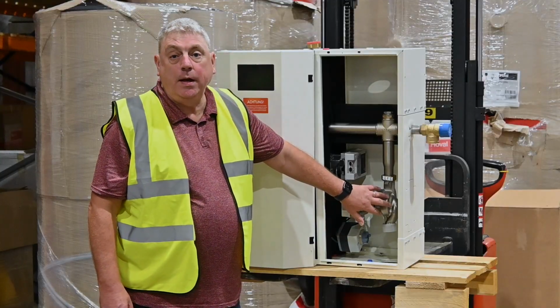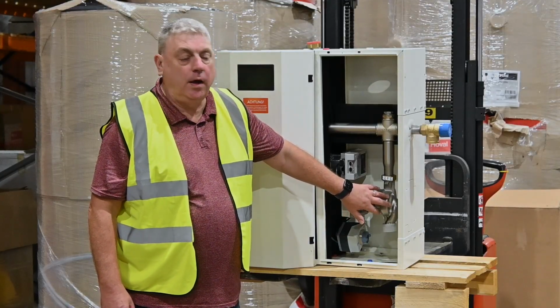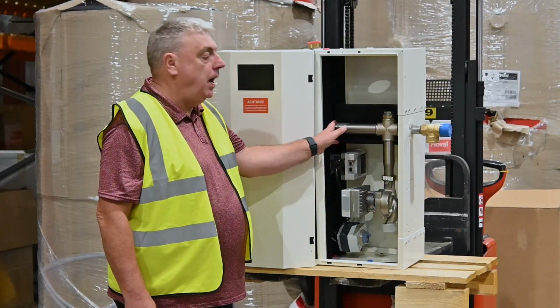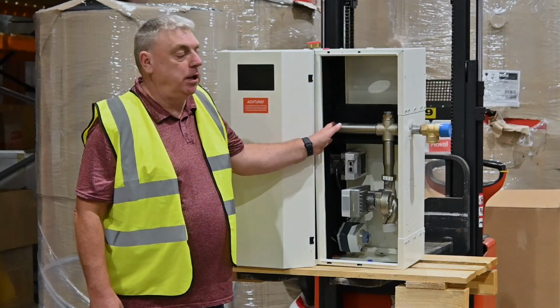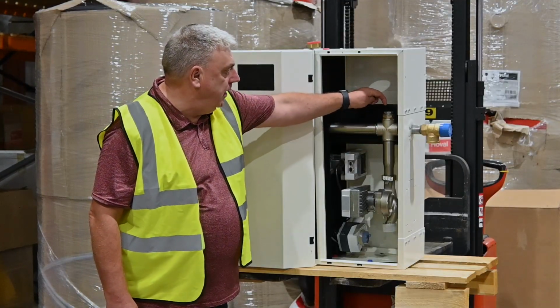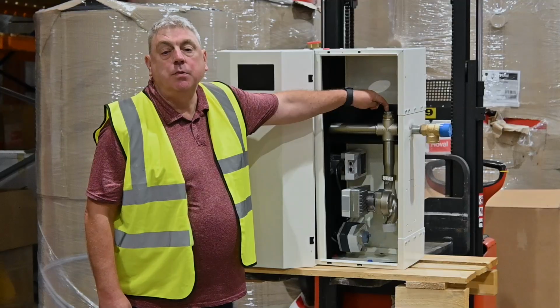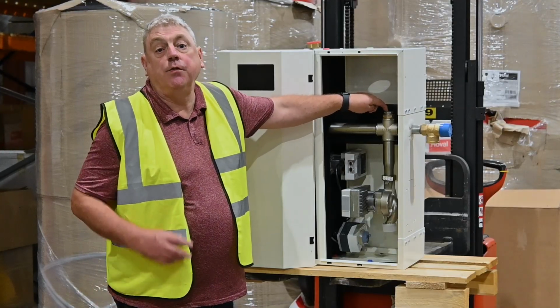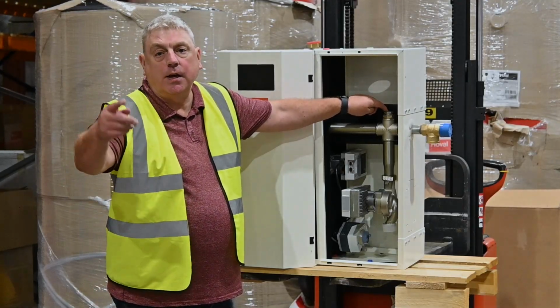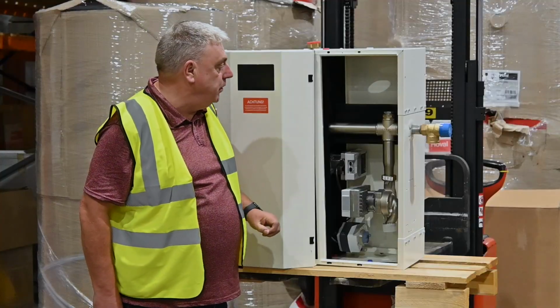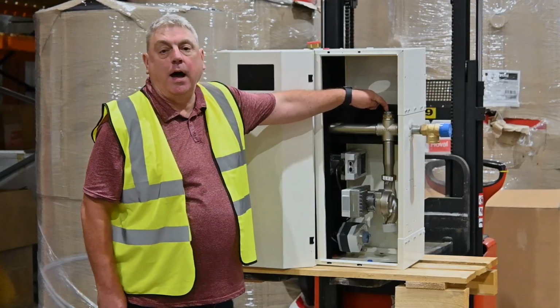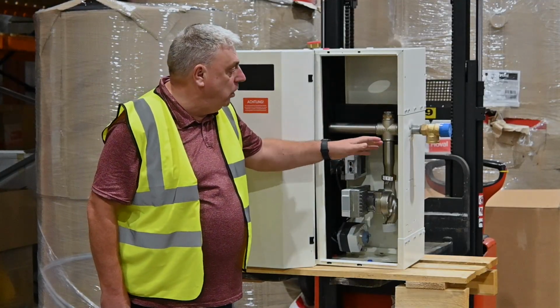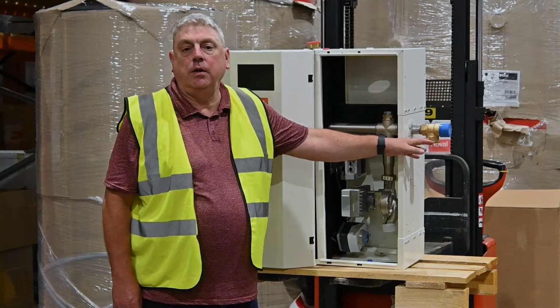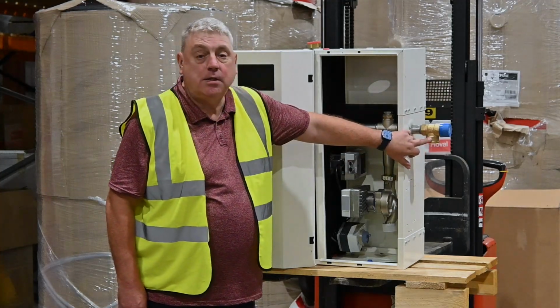Variable speed pump then will circulate the water via a non-return valve into the heat exchanger. There is an option at this point here to add some secondary recirculation. So if the site's circulating the secondary water around all the tapping devices, there's a possibility of fitting that in here. And then of course we have a safety valve on the unit which is just connected here, set to 10 bar.